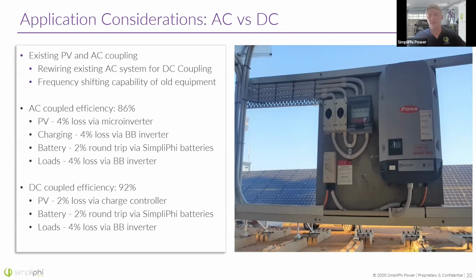However, if it's a purely AC coupled, purely grid tied PV system, no batteries, sure, that's very efficient. It's just sending power right to the grid. It's just that 4% loss from a micro and then right to the grid from there. That's it. So that's super efficient. But what I find is that's not often the customer's use case.